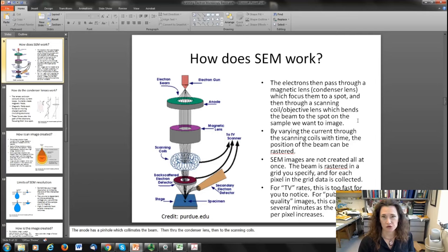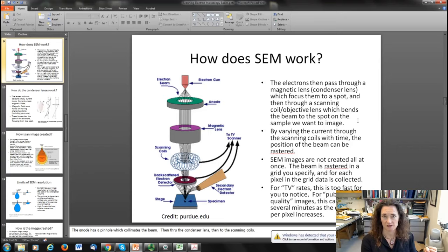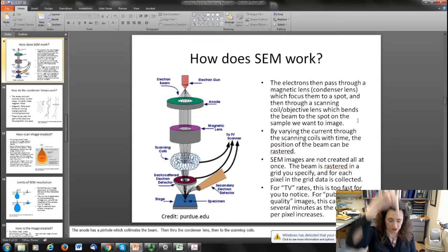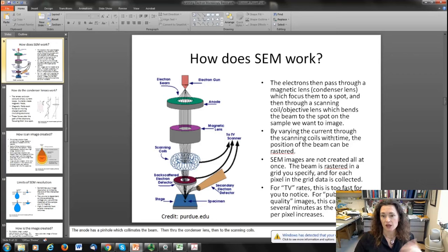Typically two condenser lenses is a standard number in a regular SEM, and then the beam passes through a scanning coil or objective lens, which is the final element that focuses the beam. These electromagnetic lenses are basically coils of wire — when you pass current through a coil of wire it generates a magnetic field, and that magnetic field creates a Lorentz force on the electrons as they move through, bending the path of the electrons to focus them.